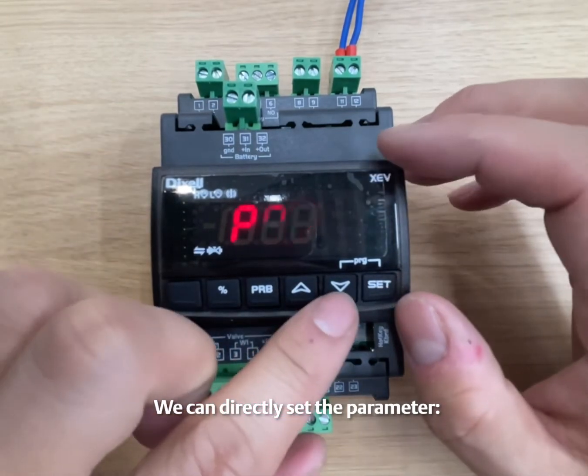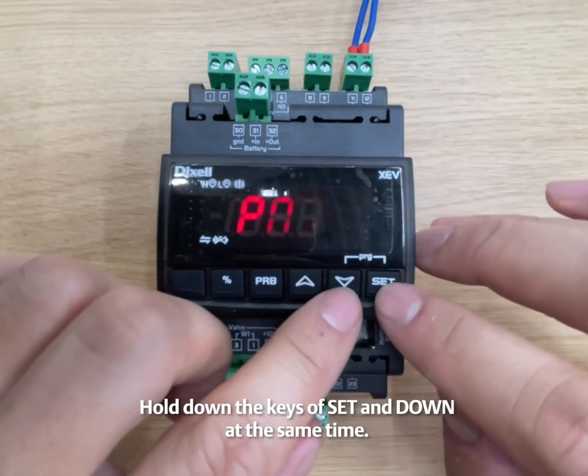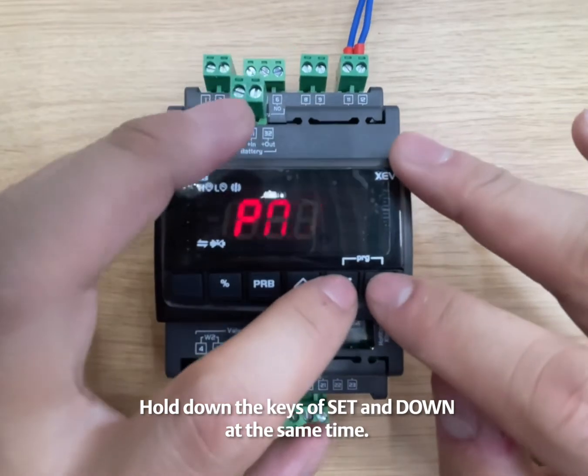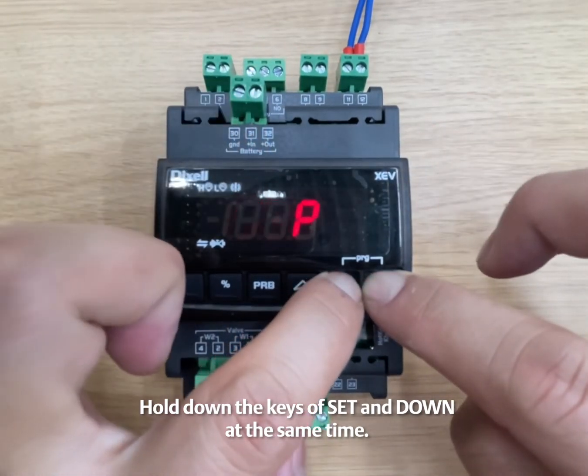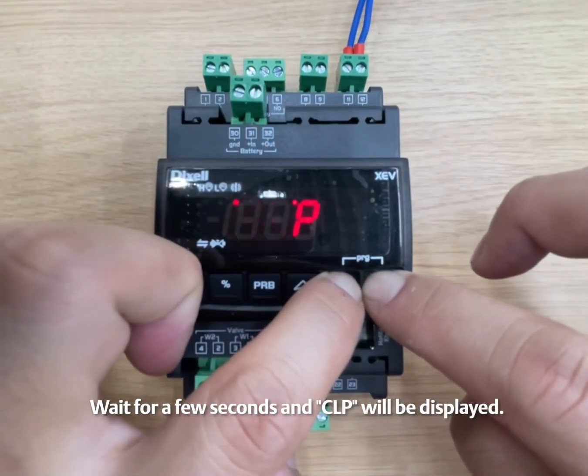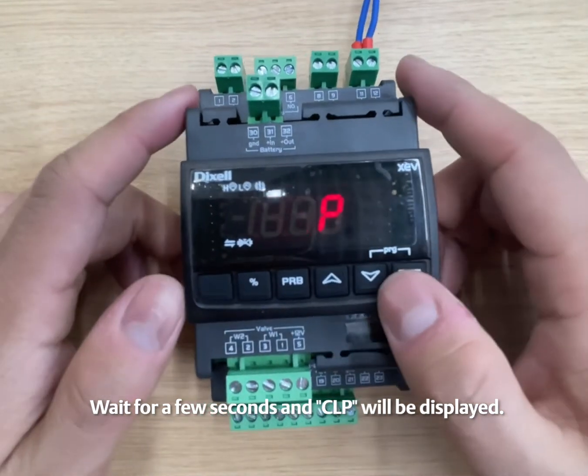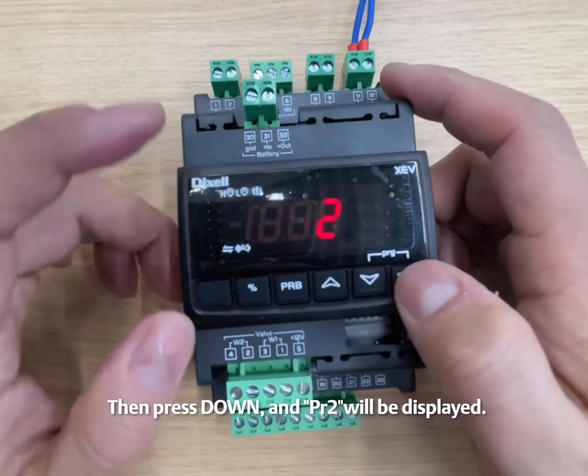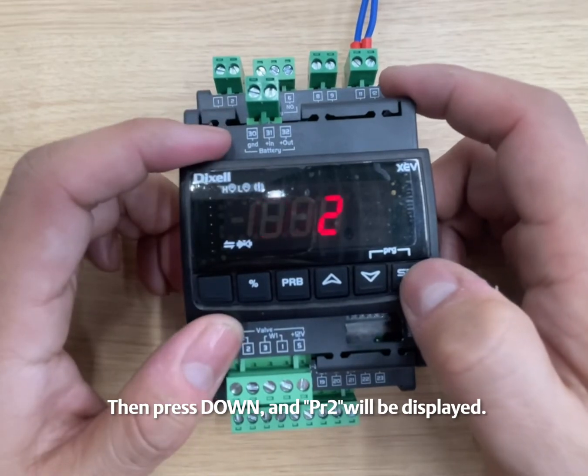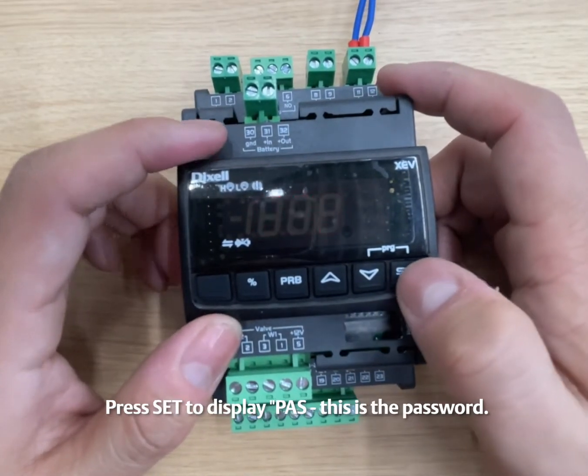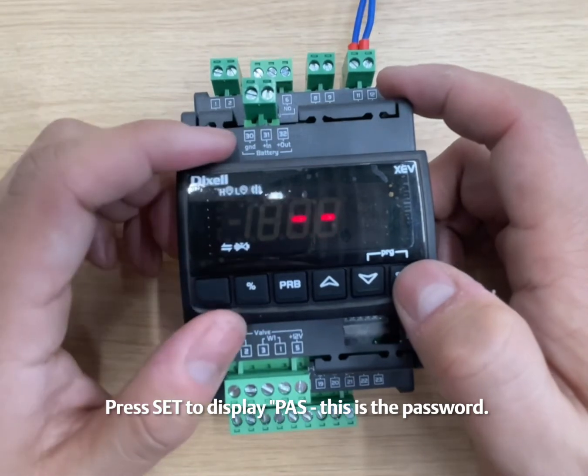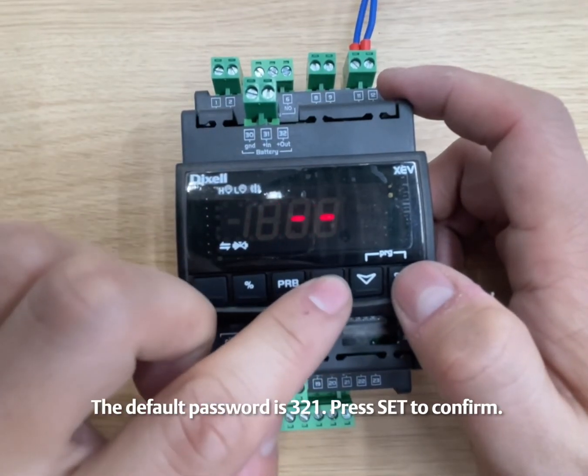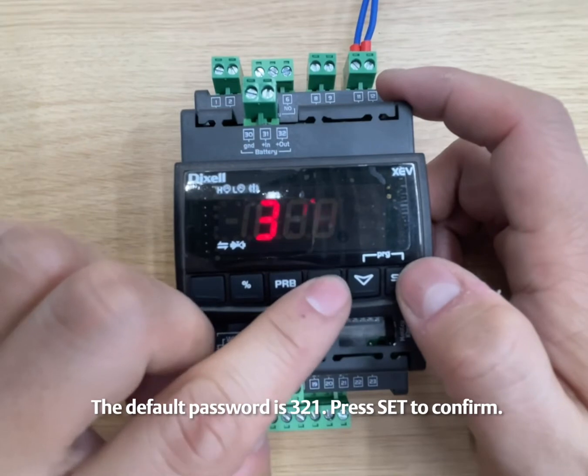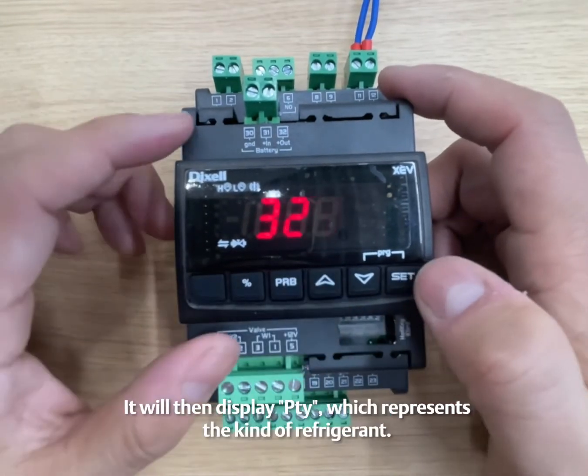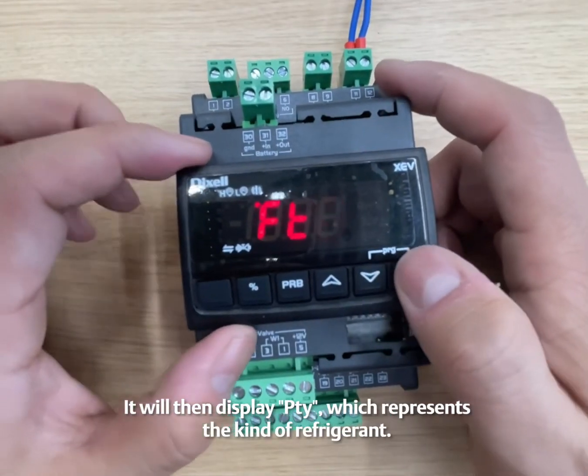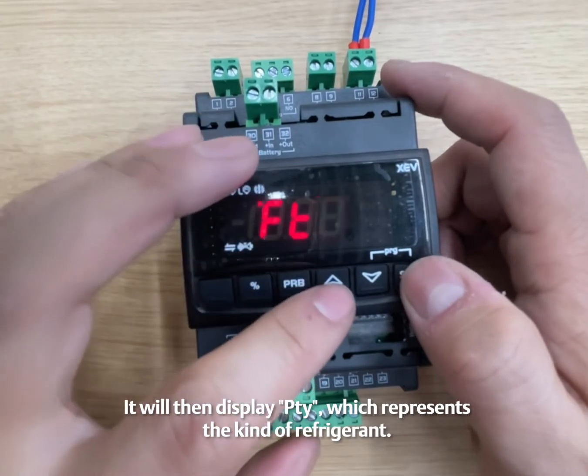We can directly set the parameter. Hold down the keys of set and down at the same time. Wait for a few seconds and CLP will be displayed. Then press down and PR2 will be displayed. Press set to display PAS. This is the password. The default password is 321. Press set to confirm. It will then display PTY, which represents the kind of refrigerant.